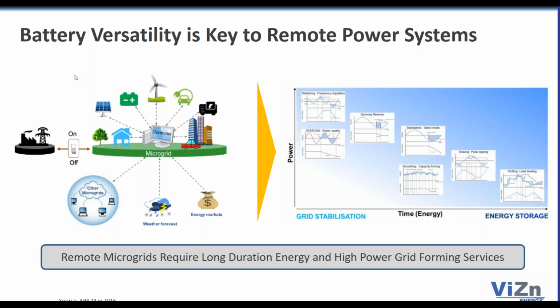That impacts the generator in several ways. First, it impacts the kilowatt hours per liter of fuel pumped through the generator. It also drives significant increases in generator O&M. So the first step to adding storage to an existing microgrid is dropping it in and letting the storage do the grid forming, letting the generator run at constant RPM. Your generators will last twice as long and you'll burn less fuel.